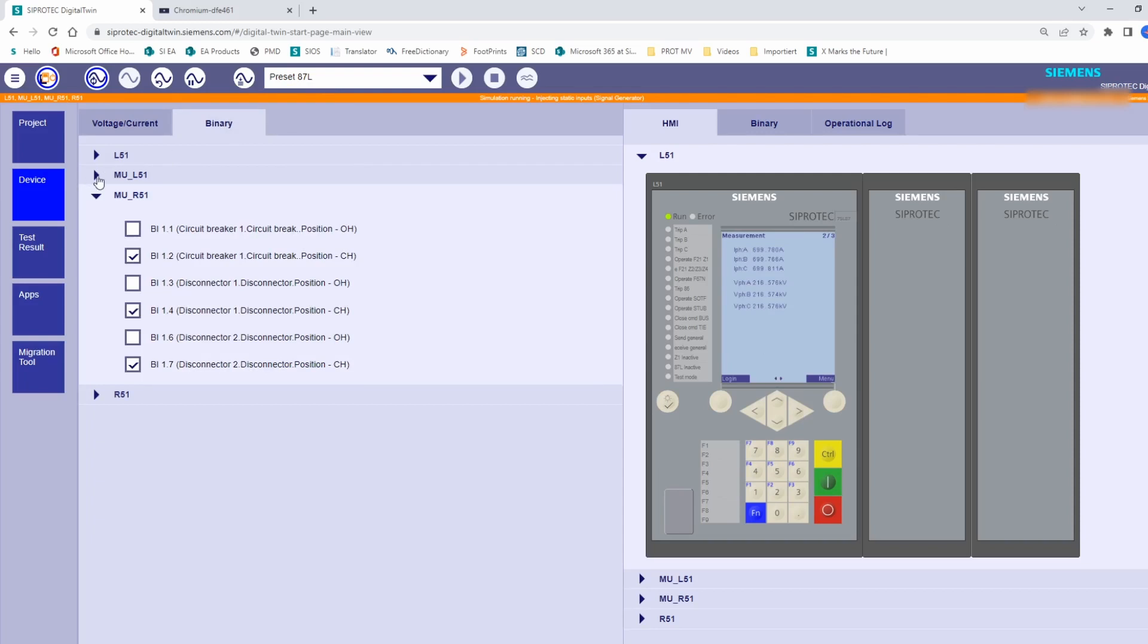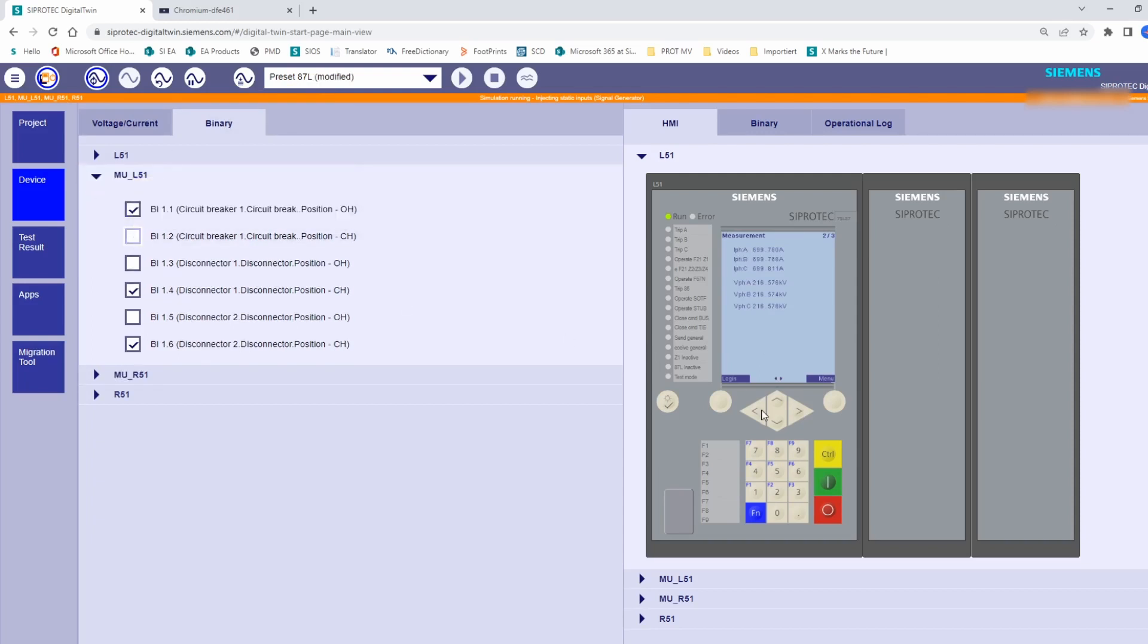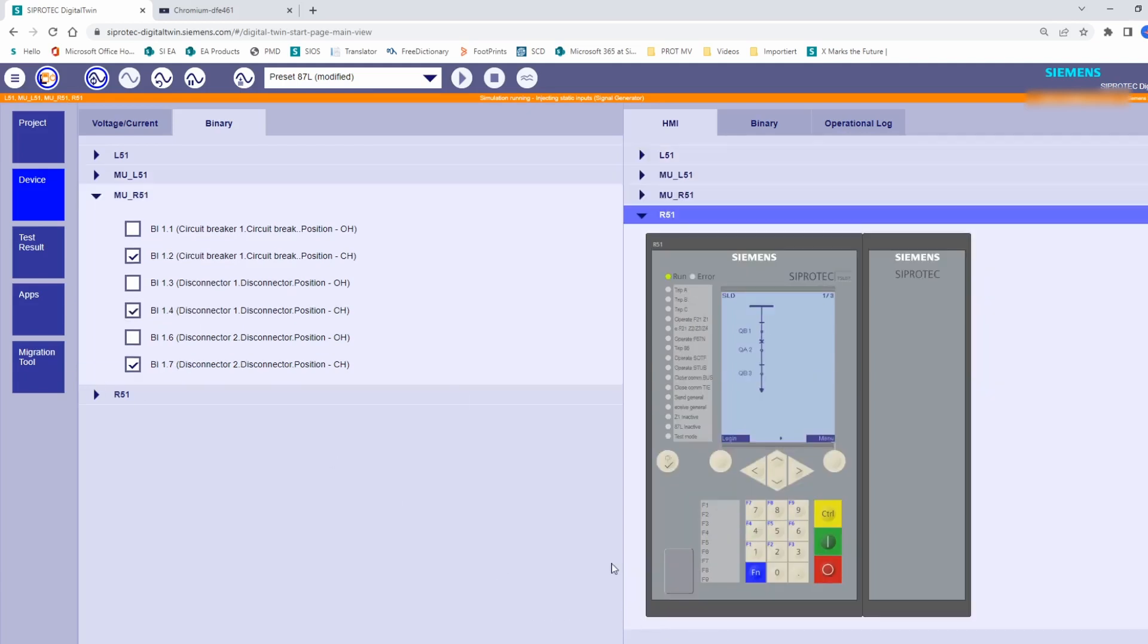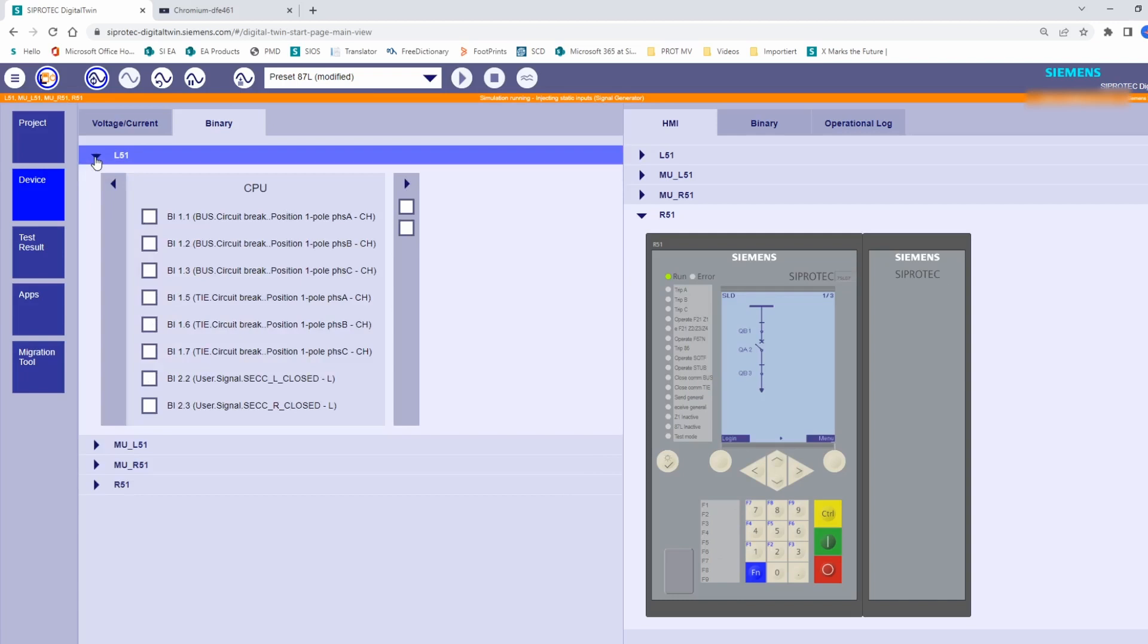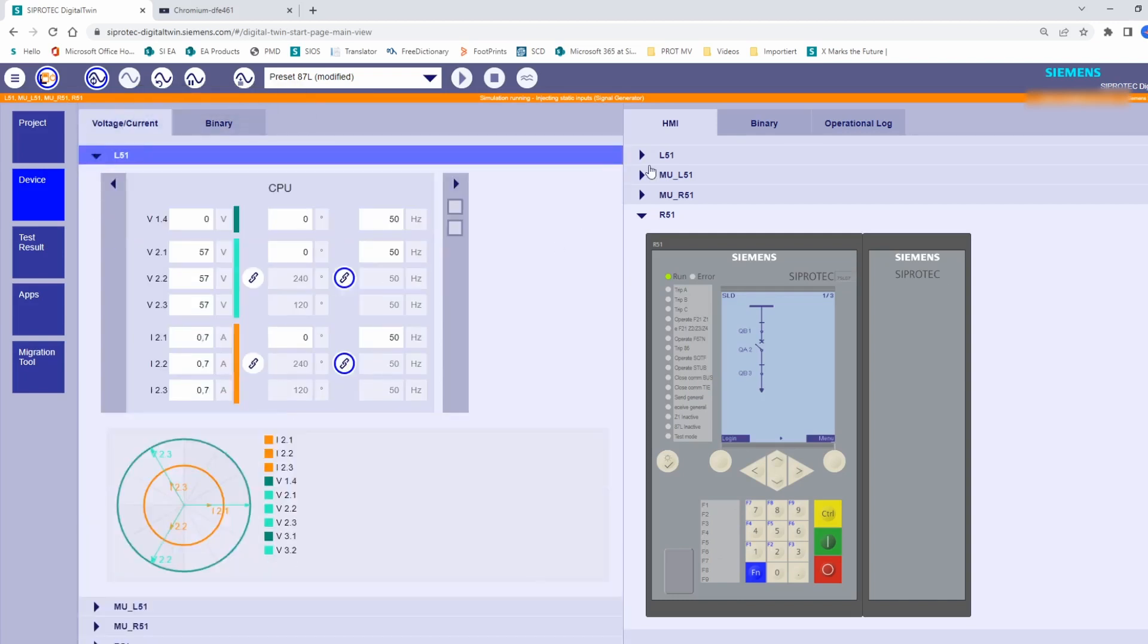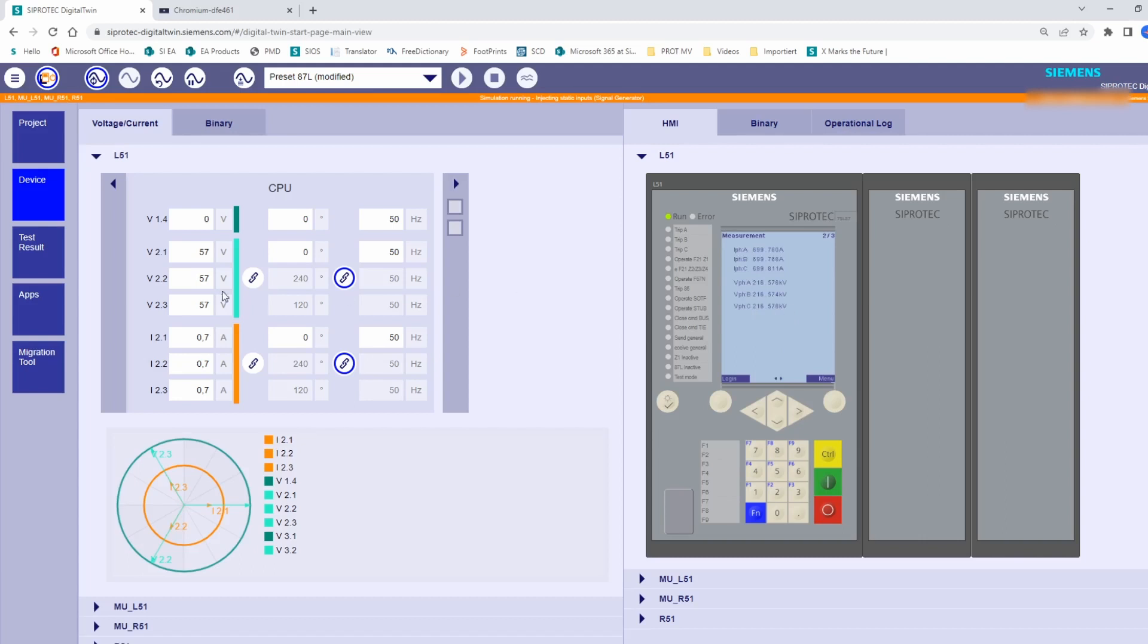If we want to test a different position, we go to the merging unit, for example MUL51, and force the binary inputs related to the circuit breaker to the open position. The change takes also effect in the display of the protection device. In this way, we can test those GOOSE messages corresponding to primary devices positions in the Digital Twin. With the static test is also possible to run some initial test to prove the right scaling and configuration of the analog values.